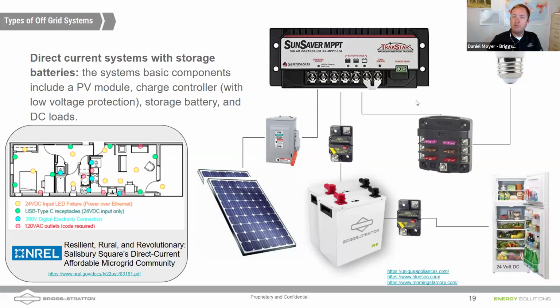120 L1 to neutral. Notice my refrigerator here, though. I didn't run this off of my low voltage disconnect. One, because this refrigerator's compressor might, on startup, draw more than the 15 amps available at that Sun Saver. And two, a lot of DC refrigerators had built-in low voltage battery disconnects internal to the system, so we can let the refrigerator shut itself off.